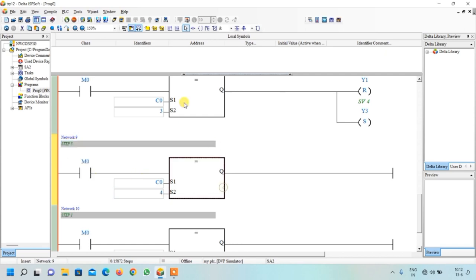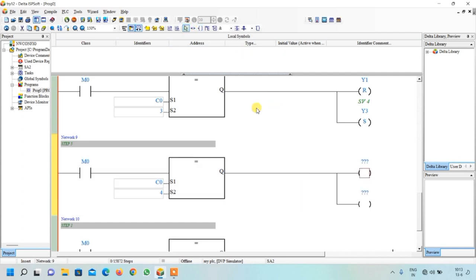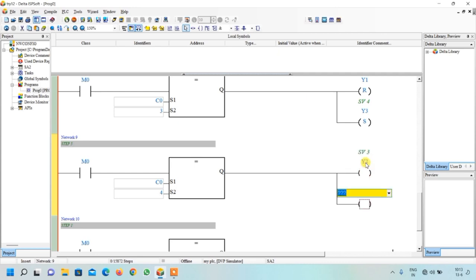For Step 5, change the comparison value to 4. After three seconds the counter becomes 4. When counter equals 4, cylinders 3 and 5 should both retract, so we need two outputs both reset: write Y2 for cylinder 3 and Y4 for cylinder 5, selecting Reset for both.